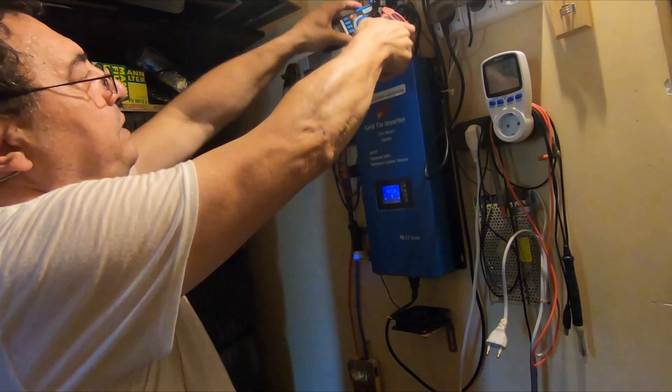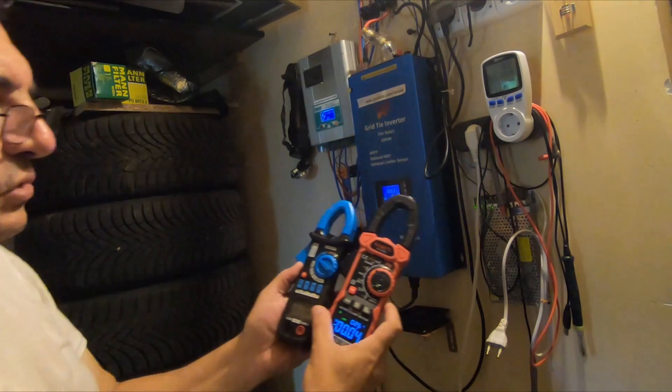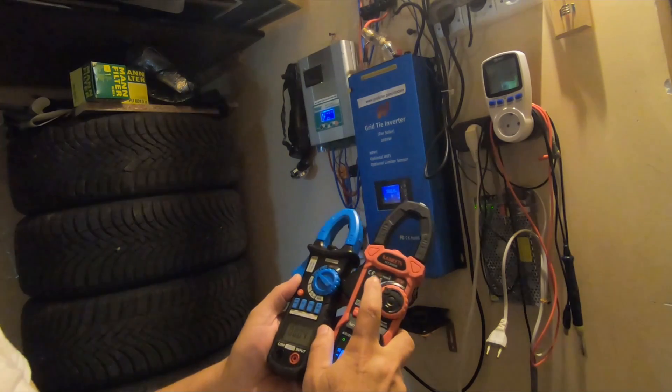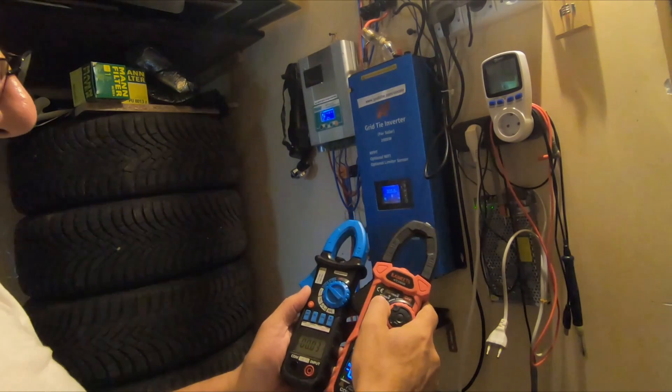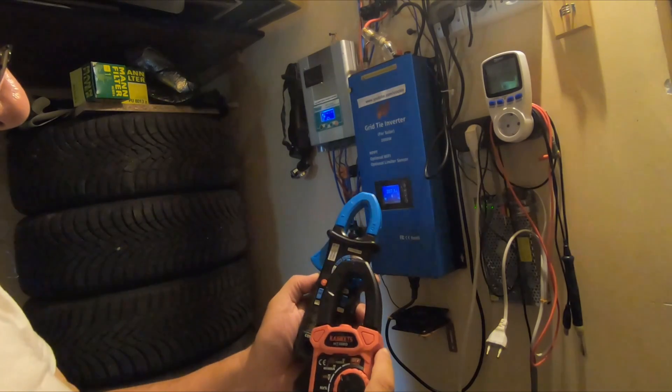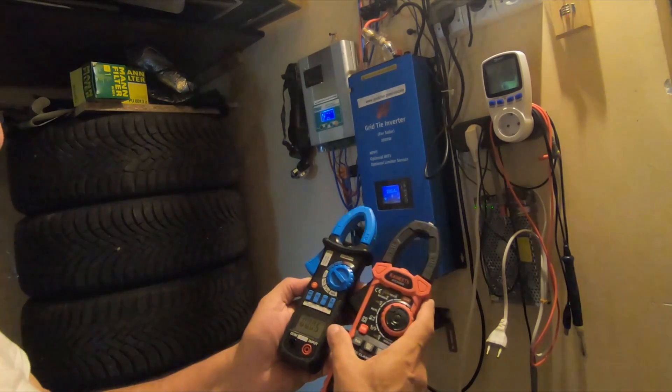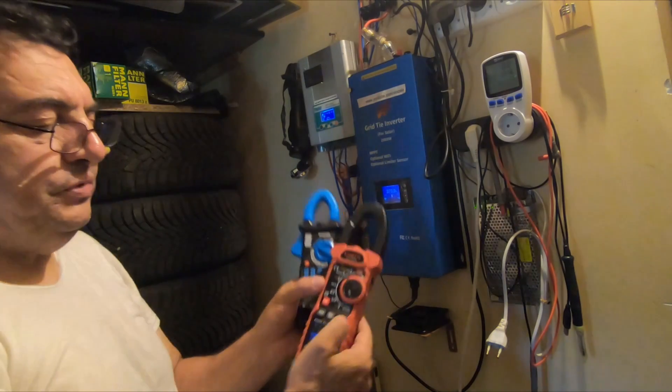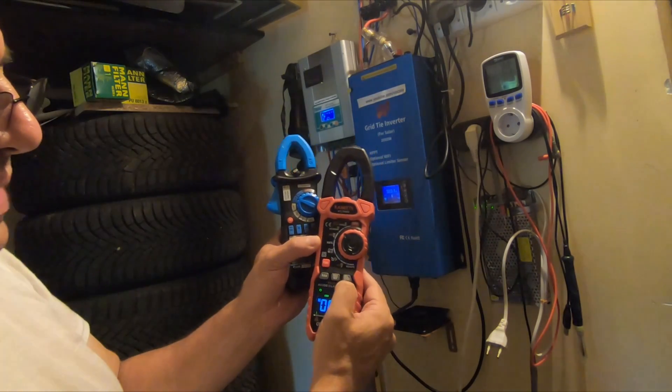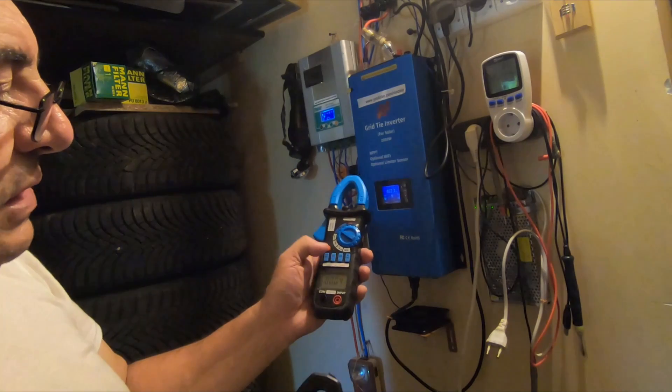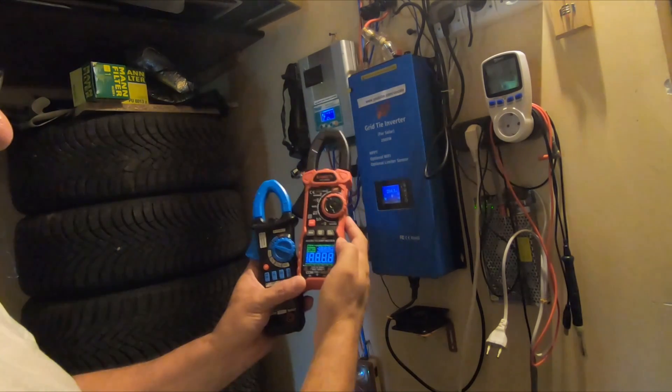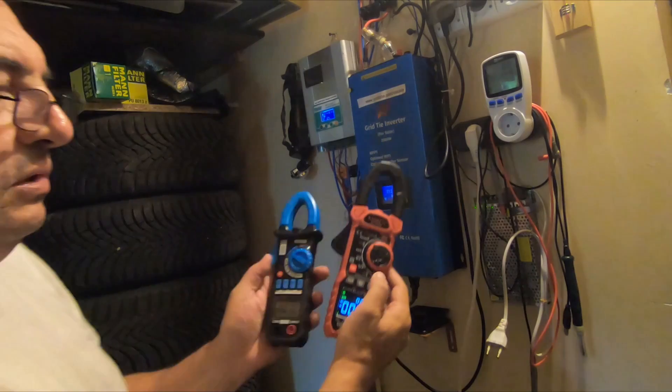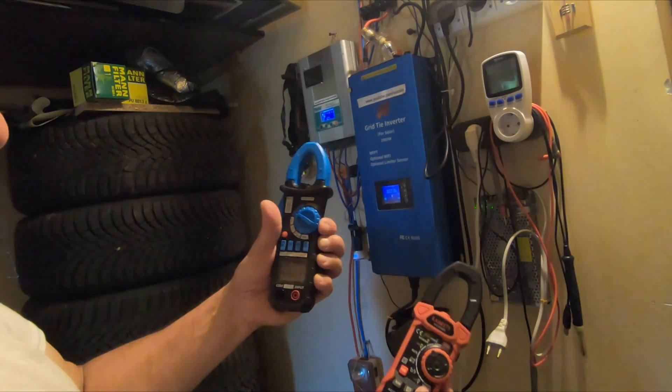Very nice. And the point is, these clamp meters are supposed to have really high currents. This is made to measure 60 to 600 amps and here we have 40 amps. Yeah, it's a kind of tolerance. Anyway, pushing this button here, REL or ZERO, and REL here, bringing the instrument on zero. That's because all these magnetic fields we have around.